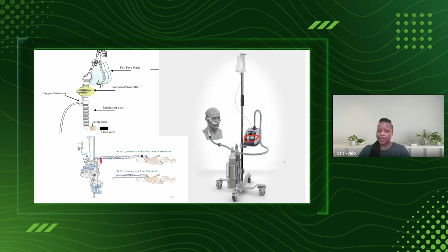Now, for active humidity, you need to have heating, and there will be water going in, so the gas can pick up that humidity. For high flow, it's the same. If I can quickly show you that picture again. Maybe Flora, you can use your pen now. There is a humidifier attached within the device, sitting on the heater plate. When you switch on the machine, the heater plate starts heating the water, and it travels through that circuit to the patient. That's how you do active humidification in high flow.